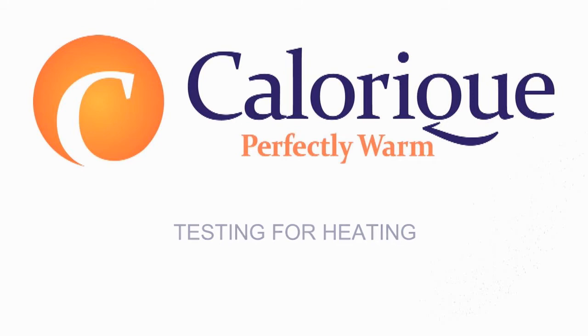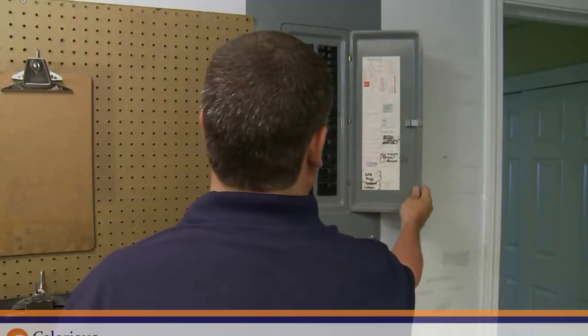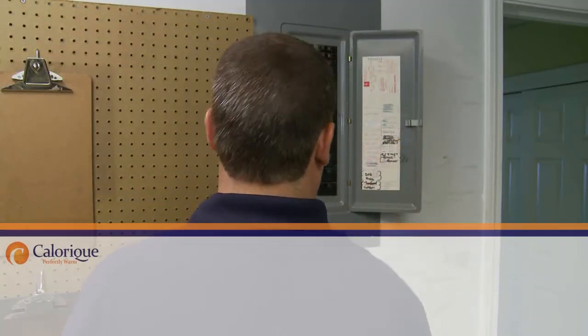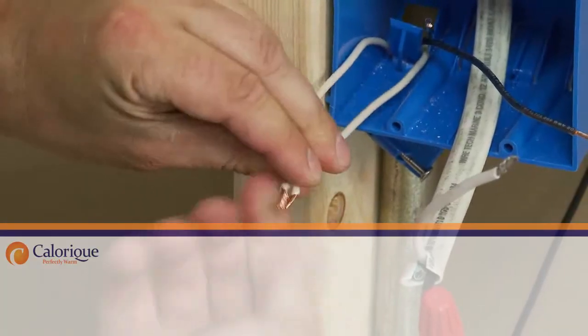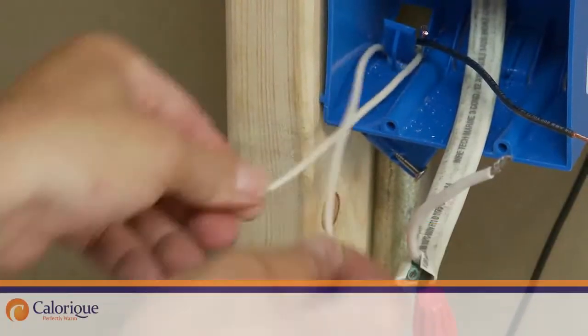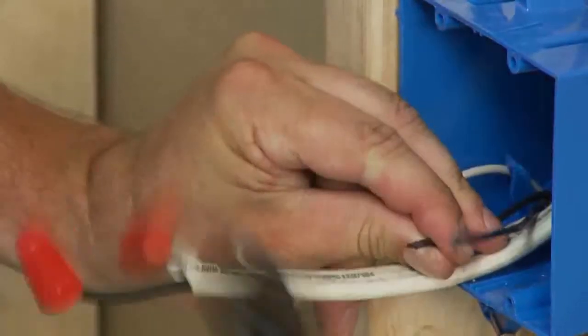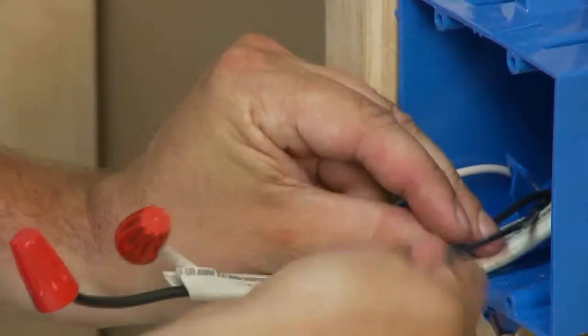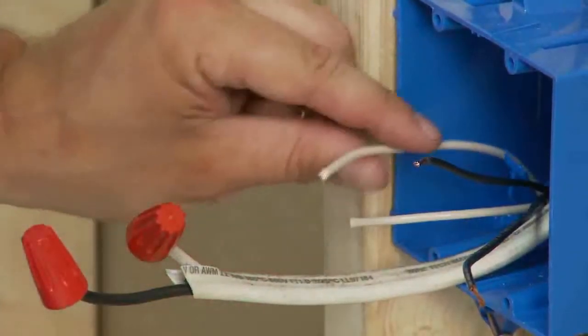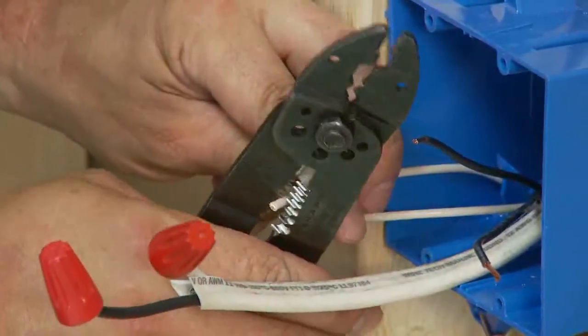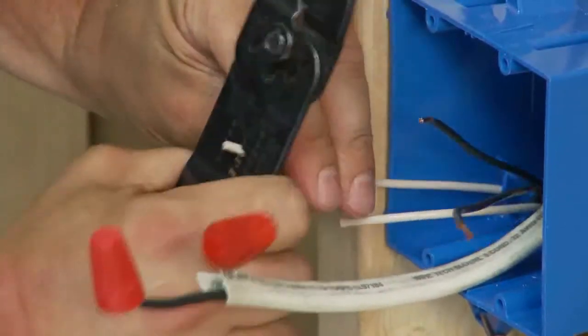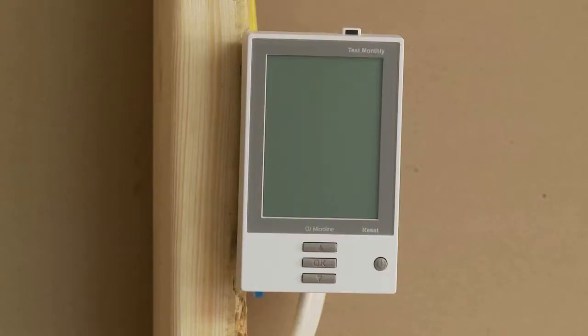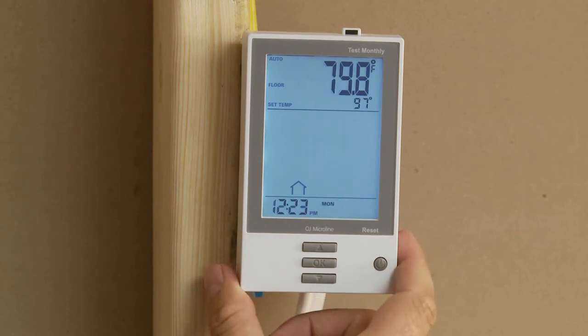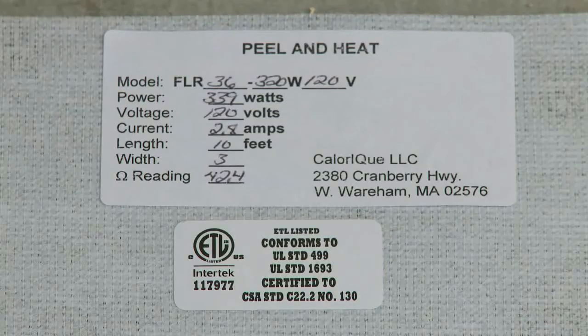Testing for heating. Note: ensure that the breaker that will supply power to the heating mats has been turned off before making electrical connections. 1. According to the manufacturer's instructions, install the control device and connect it to the electrical panel box. 2. Wire the heating mat to the junction box and wire the junction box to the thermostat. 3. Apply caution stickers provided with mats in appropriate locations.